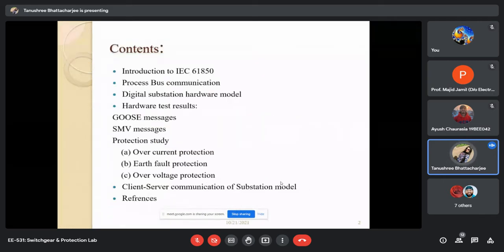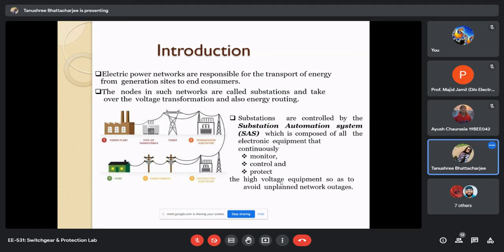So these are the contents. First, I will introduce the standard, then its process bus communication, then a digital substation model which we have implemented in Jamia Research Lab, then the hardware results we got from the hardware model, that are process bus communications like GOOSE and sampled measured values, and protection study. Three types of protection study have been done: over current, earth fault, and over voltage. We can study other protections too, but these three have been studied. Then client-server communication and references.